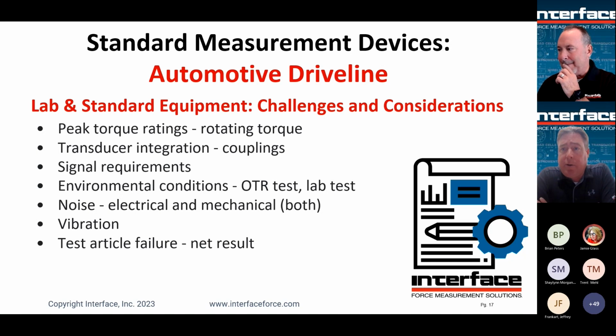And then, of course, service factor for the different drive types. If you have a diesel engine, for example, you can have a different peak torque rating than you would for an electric motor, given the actual torque profile of that kind of test. Secondarily, you have to consider how you're going to get that transducer into that rotating assembly, making sure you have the correct couplings. There are a lot of considerations there and a lot of ways to do that. Typically, we recommend smooth shaft type bores with clamping hubs, but some folks do prefer keyed shafts, things like that. There's a lot of different considerations there to keep in mind.